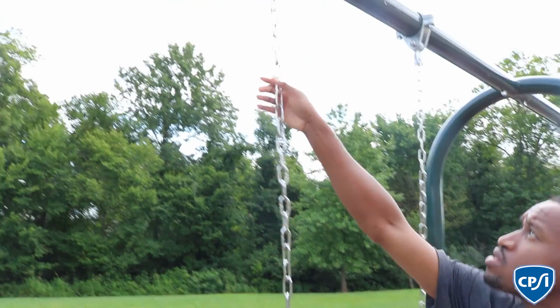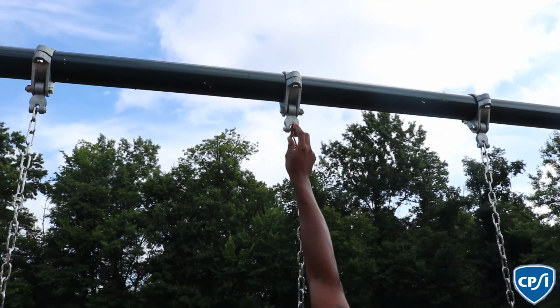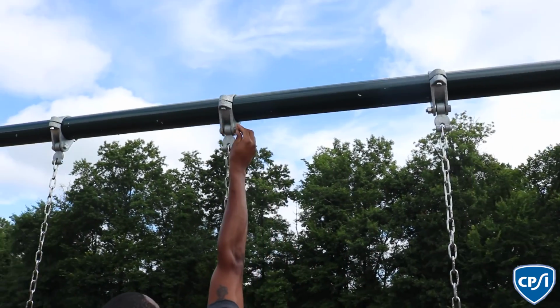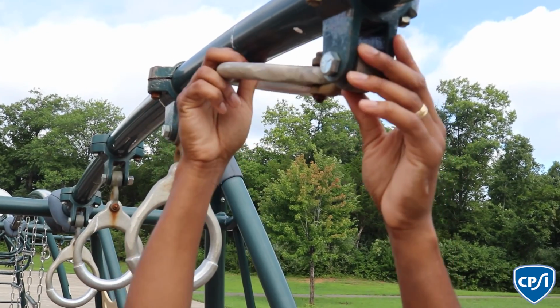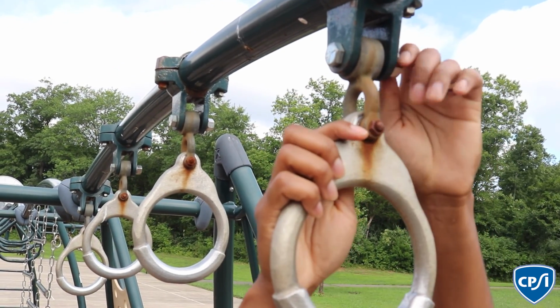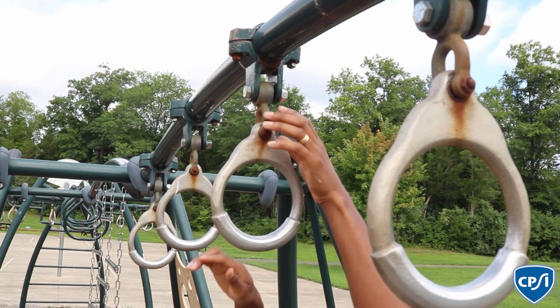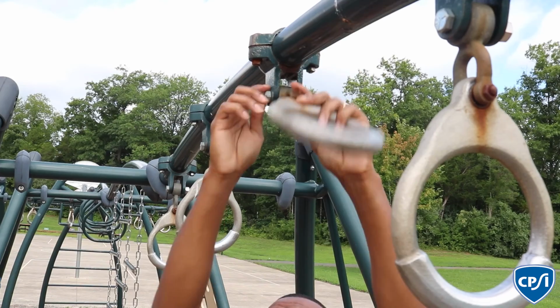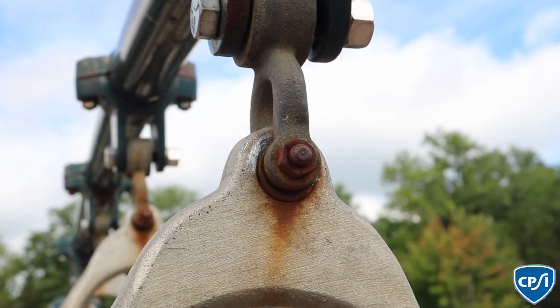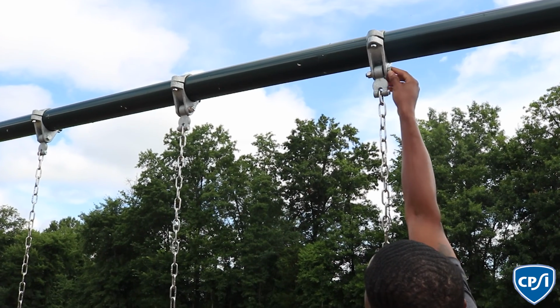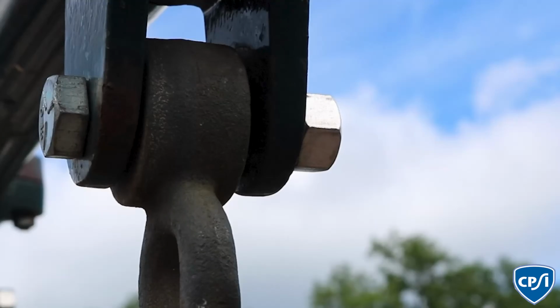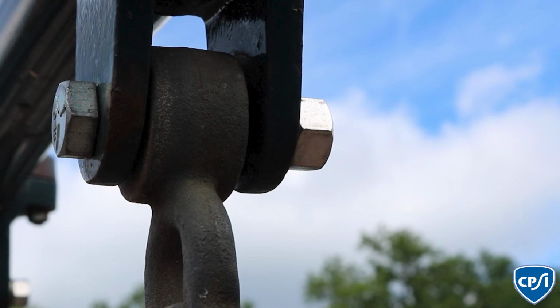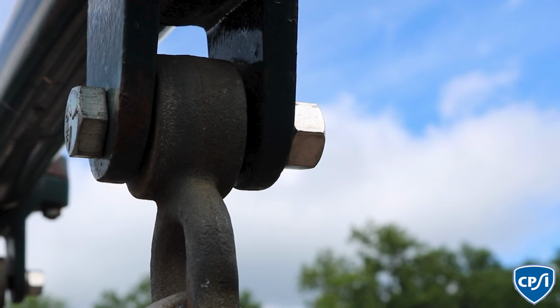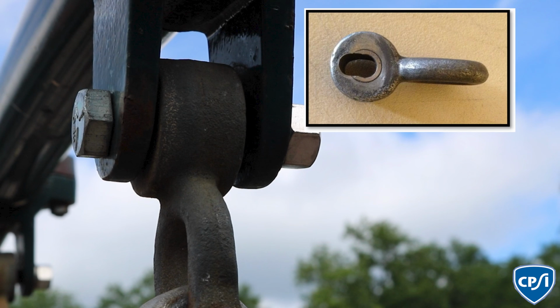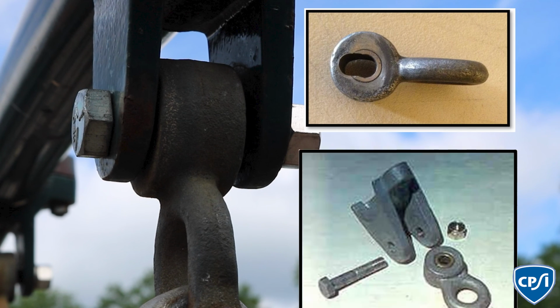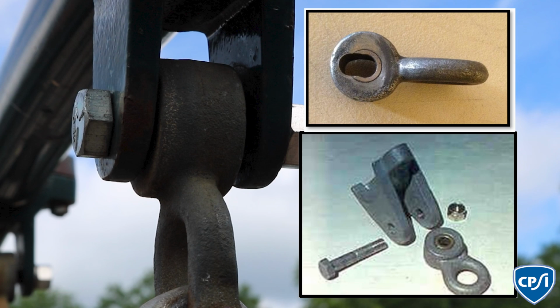Continue with the inspection by examining the hardware and fasteners. Hardware and fasteners should not loosen or be removable without the use of tools. If exposed to the user, the hardware and fasteners should be smooth and not likely to cause a laceration, penetration, or entanglement hazard. Hardware and fasteners should be corrosion resistant and be selected to minimize corrosion of the materials they connect. Equipment with bearings or bushings used in moving joints should be easy to lubricate or be self-lubricating. Self-lubricating bushings are designed to wear out and should be regularly inspected and replaced.